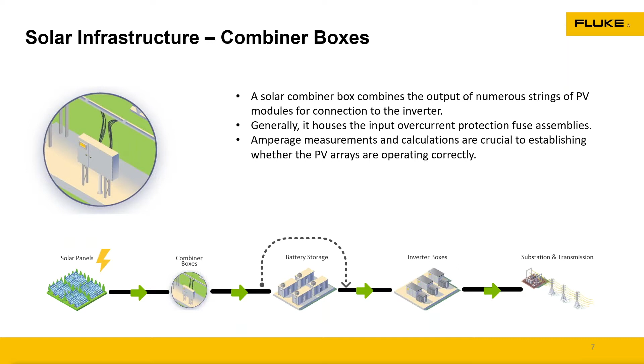This is where you're going to see short failures, short circuit failures, something of that nature where it's popped the fuse. This is kind of the go-to for the technician out in the field—he'll be able to establish if he's got equal amperage or voltage coming off his lines, and from that point go back to those solar arrays and see which one potentially has a fault or isn't generating properly.